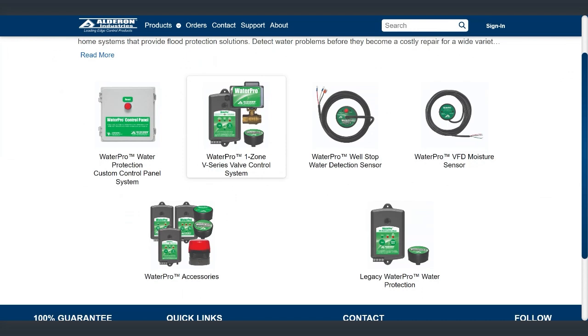That one is designed to connect to your well system, your pressure switch on your well. Set that next to your well tank or your pump area down in the maintenance room. If you detect a leak with that, then that'll interrupt the signal to your pressure switch, cutting off your well pump, so it's not going to continuously pump up water and flood your area. That's a simple push button reset. And then we also have a sensor that connects to a VFD. So it just goes to the digital inputs on your VFD. If it detects water, it shuts down the VFD. And then we have a couple different accessories and then legacy items there.